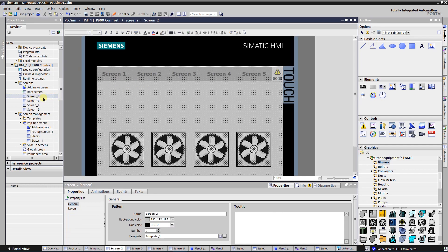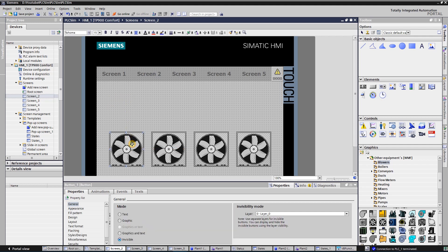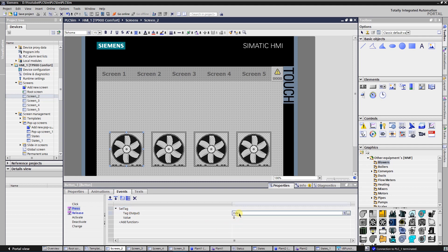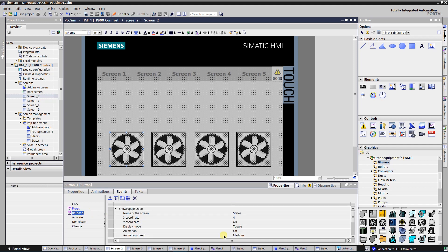Create a new screen and drag and drop some blowers from your graphics library. Put a button on each graphic and in the general properties select mode 'invisible'. Switch to the events tab of the button. Select the button press event and set the index tag value to 0. This means that when this button is pressed, the elements of the array with index 0 will be accessed.